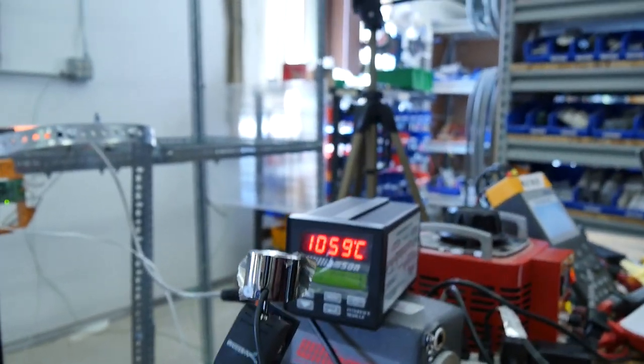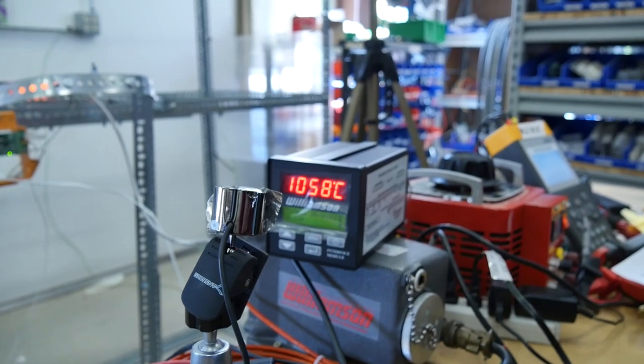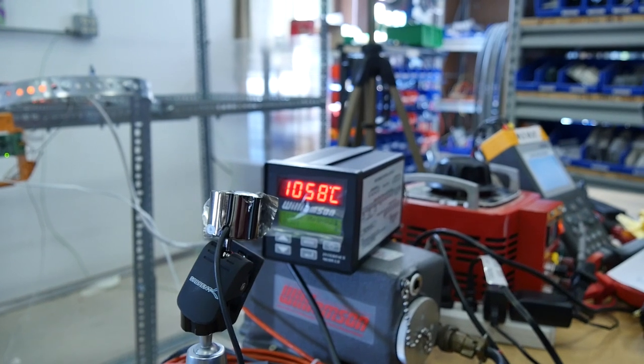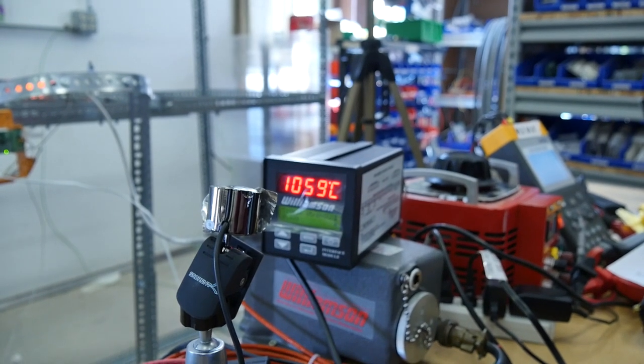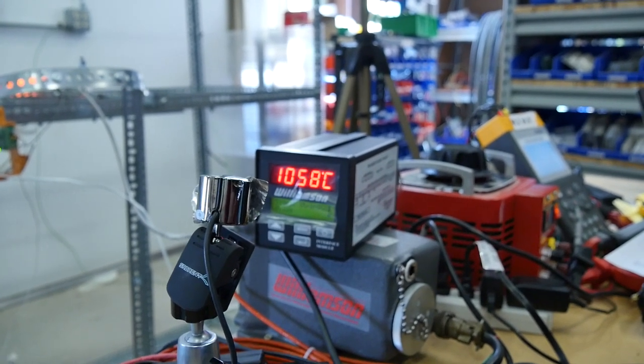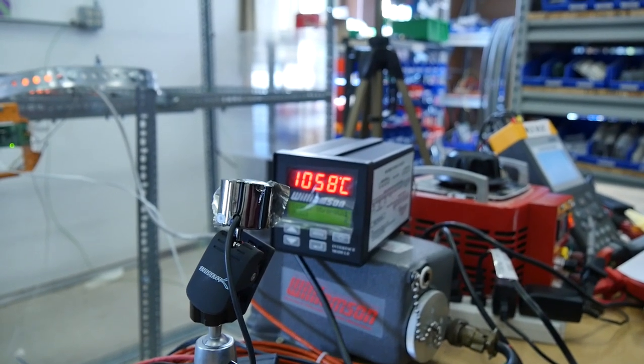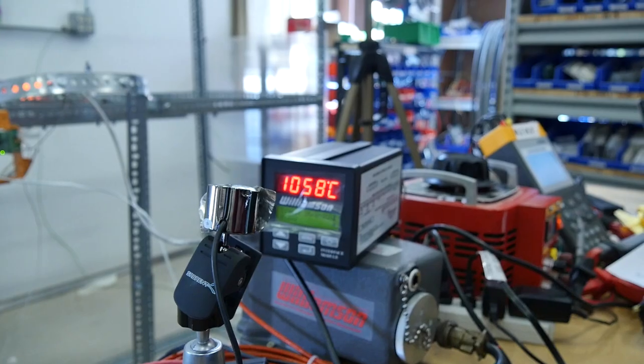So it's taking the high temperature and the lower amount of reading and calculating a lower emissivity. And this is because this ceramic is partially transparent at the wavelengths that the Williamson is measuring, which is 2 to 6 microns. Isn't that right? Yeah. So the internal thermocouple, the B-type internal thermocouple, is currently reading 1,122 degrees C, and the Williamson is seeing 1,058 degrees C.